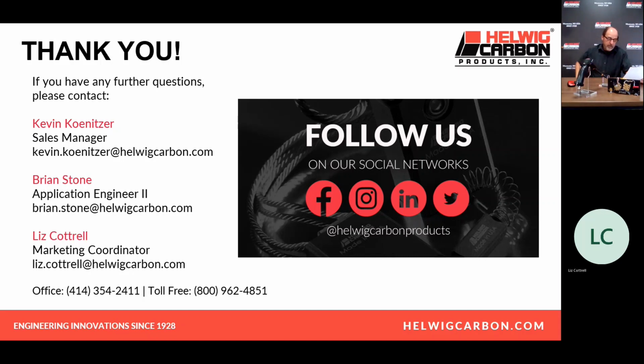Not a problem. Diesel-driven engine. How can we prevent voltages getting to engines, crankshaft, and bearings? This is not something we do every day, but we have done this a number of times. I specifically have. Again, if we can find a place to put our kit, which we always can, and we can get the ground, determine which is the correct ground, because remember, there are multiple ground planes. Grounding is more complex than it seems on the surface. We can pull those voltages away, whether it's a diesel engine driven or a gearbox or harsh duty or just a standard install. It's all the same. We're doing the same thing. It's just that the method we use might have to be tweaked because of the very unique situations we bump into. But typically, we're talking about putting a brush on the source, getting it to the proper ground.